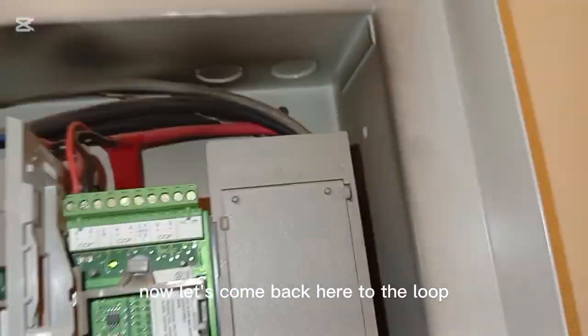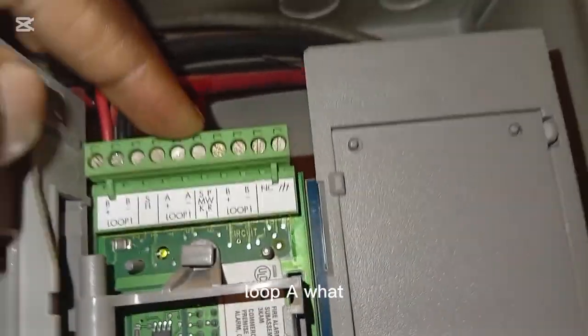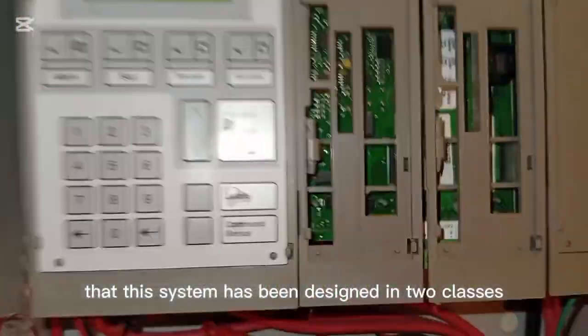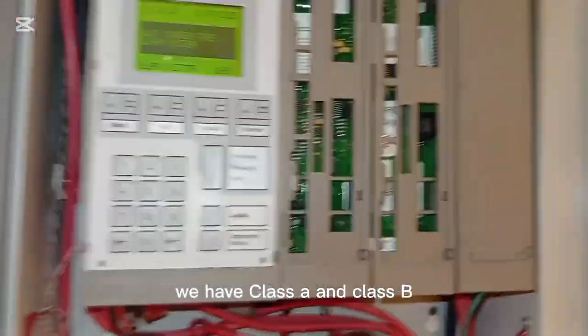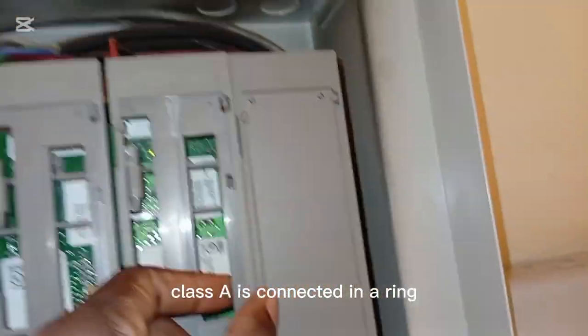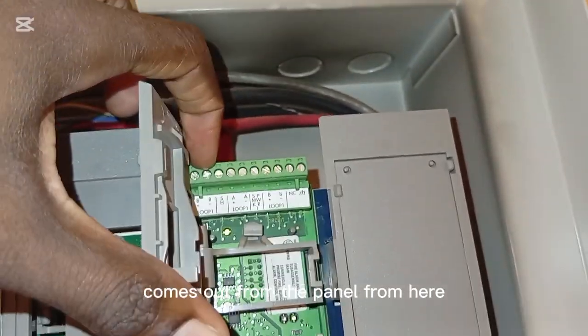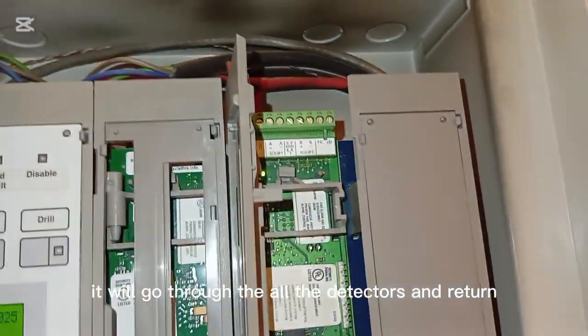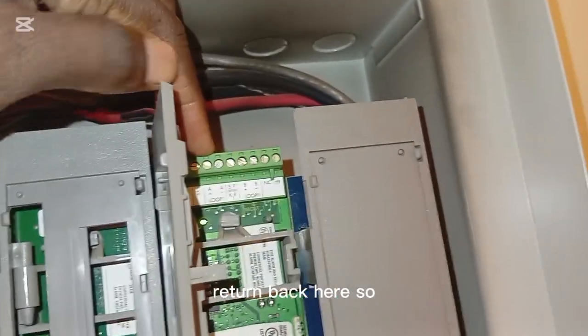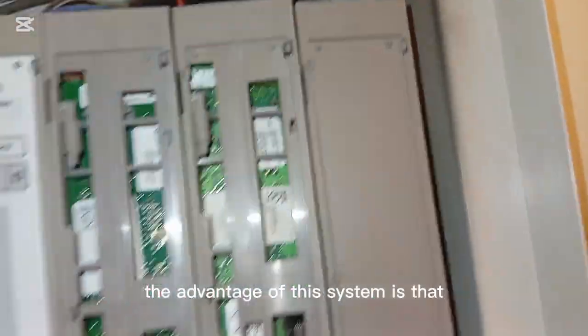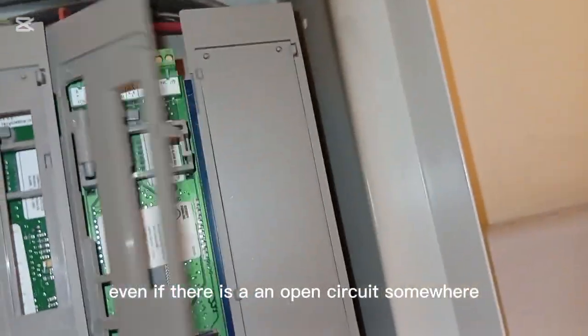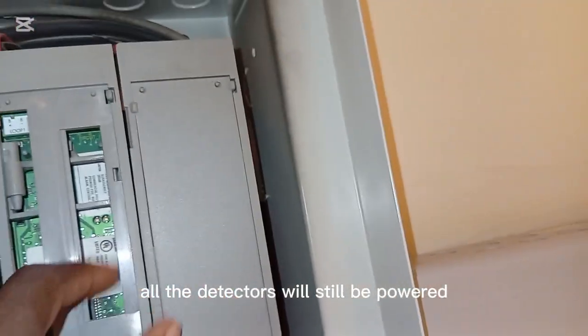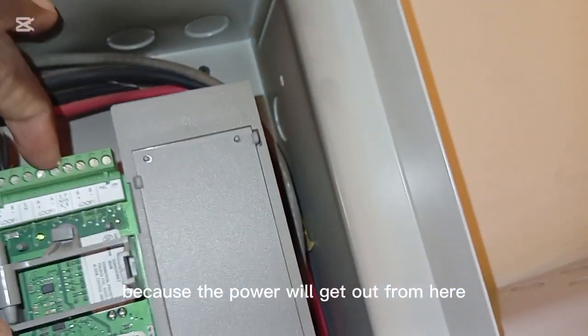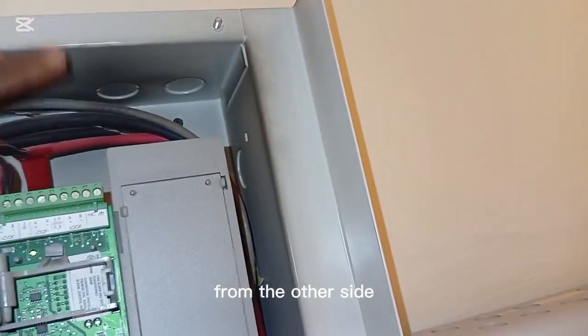Now let's come back here to the loop. You can see here we have loop A, loop B. What it means is that this system has been designed in 2 classes. We have class A and class B. Class A is connected in a ring. What do I mean? If my input comes out from the panel from here, it will go through all the detectors and return back here. So the advantage of this system is that even if there is an open circuit somewhere, all the detectors will still be powered, because the power will get out from here and will also get out from the other side.